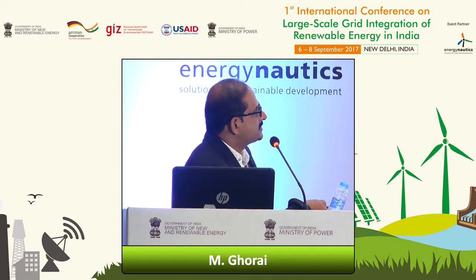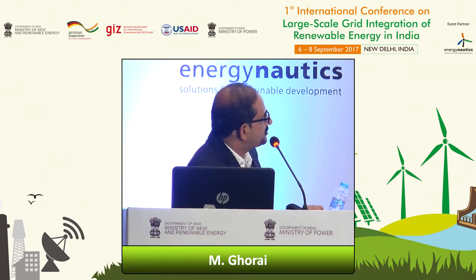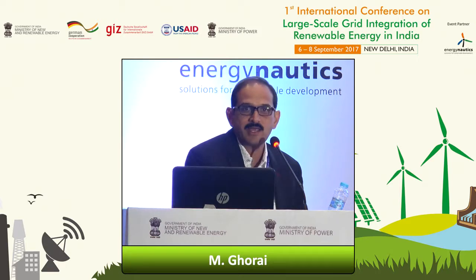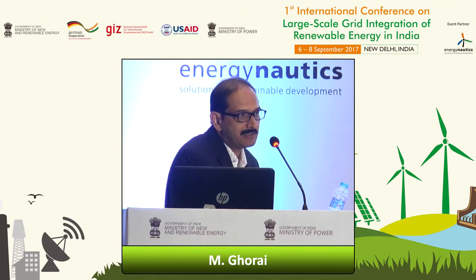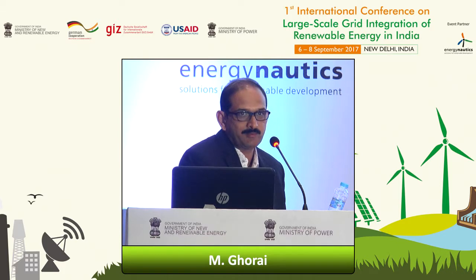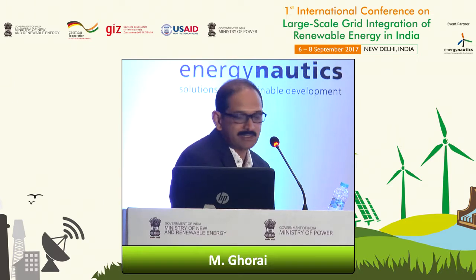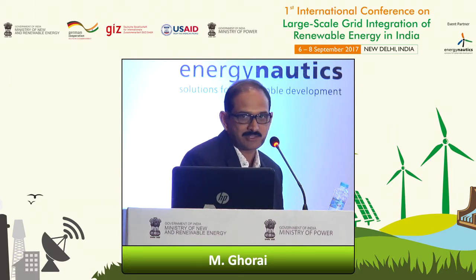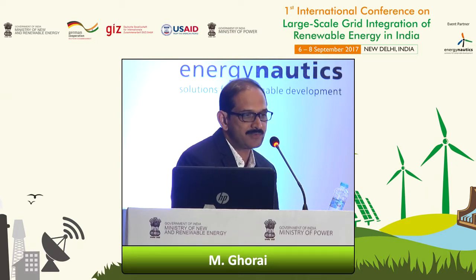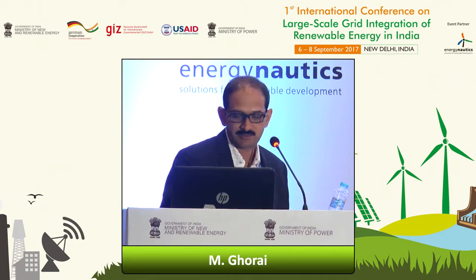Okay, this is the DVAR controller, the control cabinet, and this is the wind park controller. You can make the DVAR controller or the STATCOM controller the master controller, or you can also make the wind park controller the master controller. Depending on the individual wind farm requirements and the requirements from the operator, we can do both options.